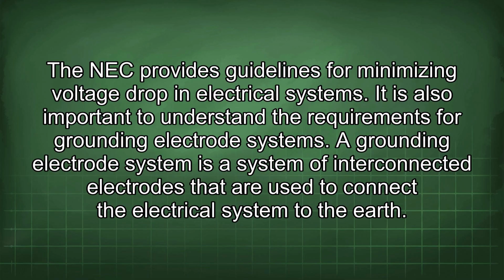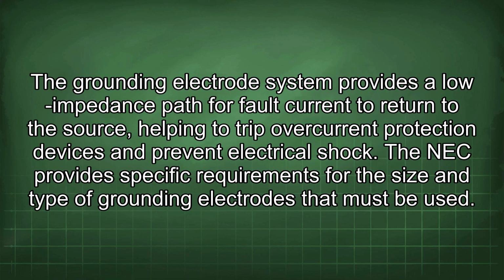It is also important to understand the requirements for grounding electrode systems. A grounding electrode system is a system of interconnected electrodes that are used to connect the electrical system to the earth. The grounding electrode system provides a low impedance path for fault current to return to the source, helping to trip overcurrent protection devices and prevent electrical shock. The NEC provides specific requirements for the size and type of grounding electrodes that must be used.